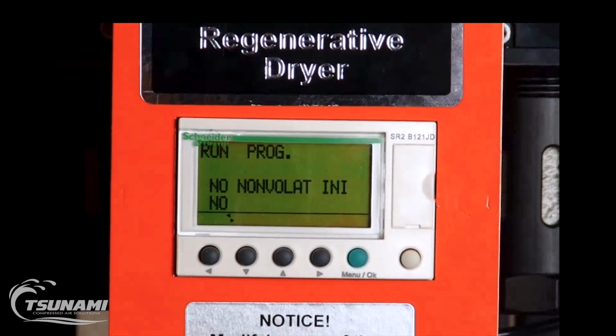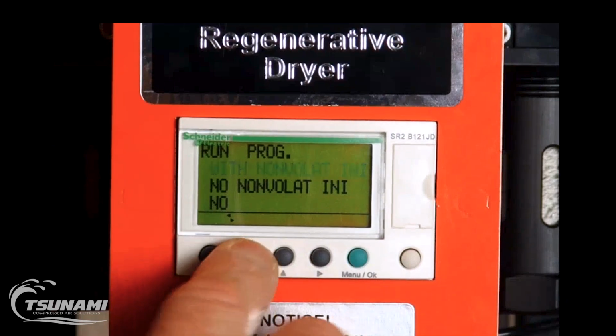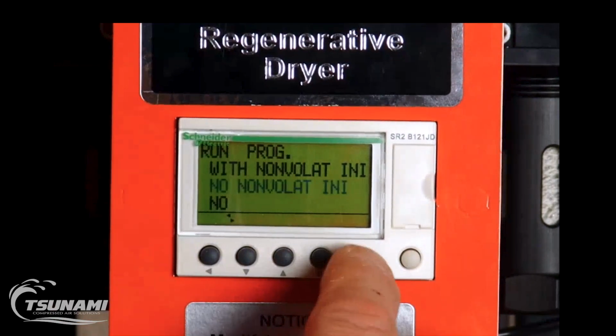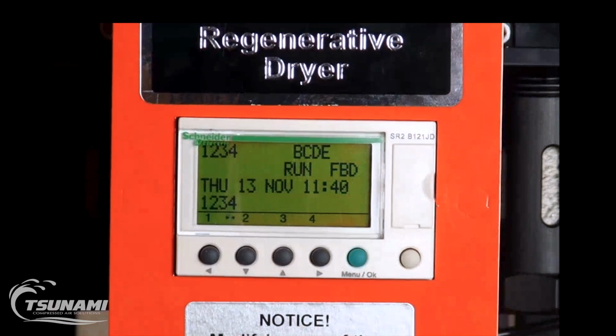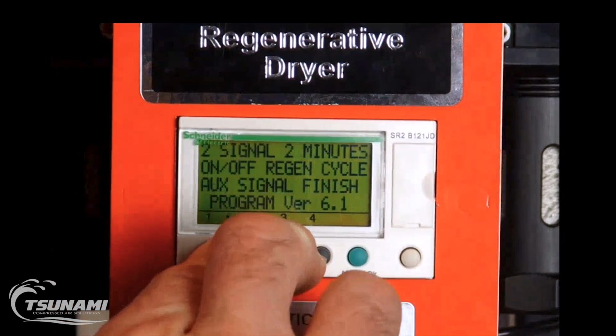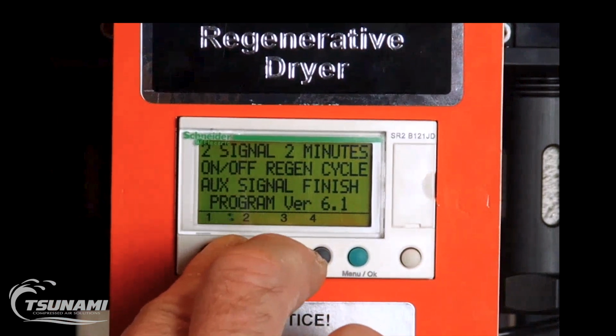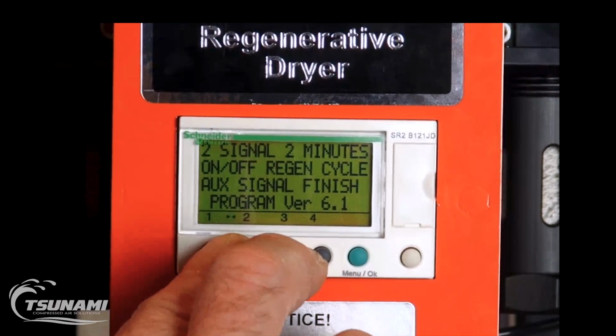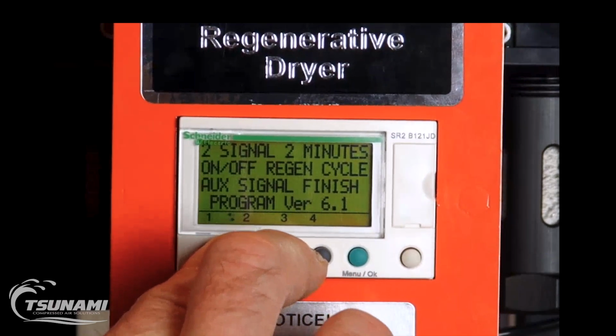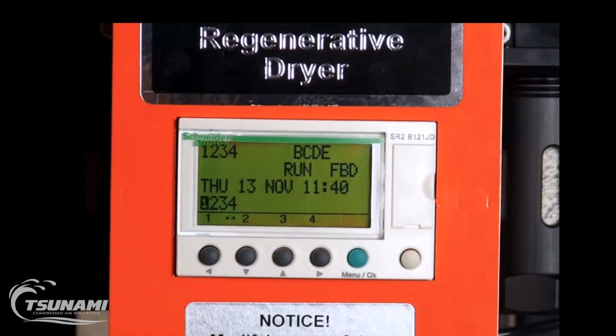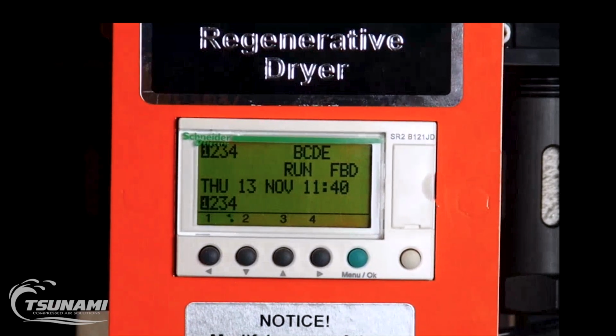Since we've uploaded a new program, it doesn't really matter, but it's just good habit to get into: don't reset any of the timers or latch values. And now, as you can see, it always is going to default to a 10 horsepower system. This is program 1. What program 1 says is that even if you receive a signal from a digital input to tell this PLC to stop running, the dryer is going to complete its drying cycle.